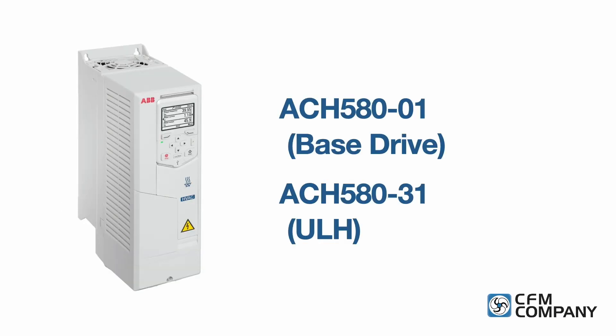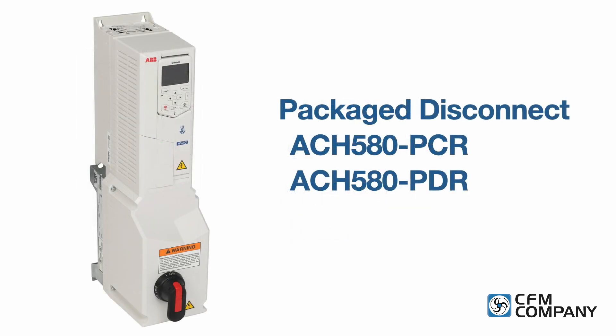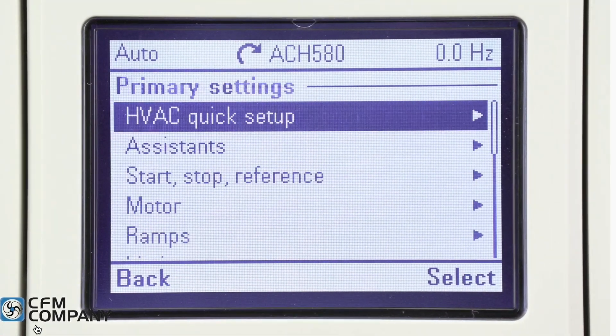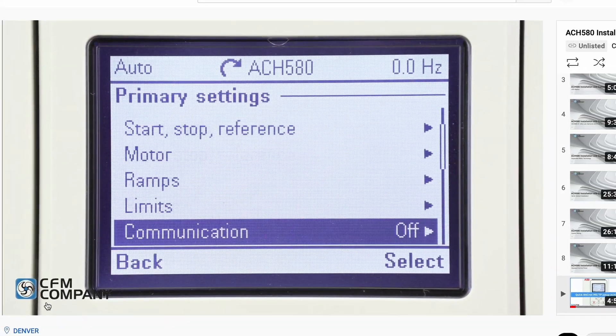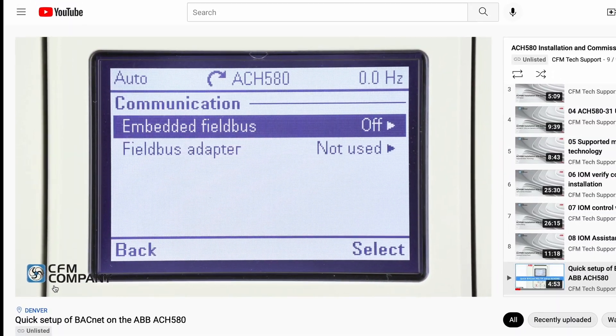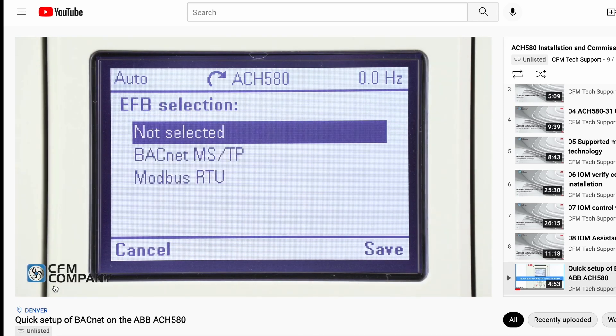Please be aware if you're working on an ABB ACH 580 base drive, dash 01, or a drive with a package disconnect, a dash PCR or a dash PDR, the BACnet MSTP is configured through the primary settings menu of the main control panel. To learn more about the basics of BACnet MSTP and how to program the ACH 580 base drive, please watch the video, Quick Setup of BACnet on the ACH 580.